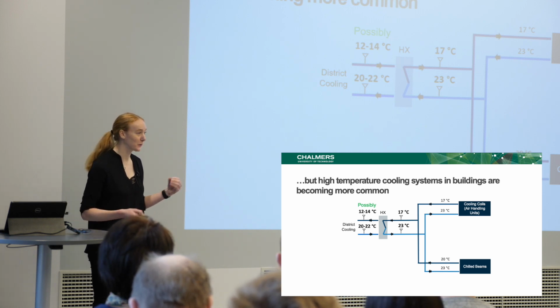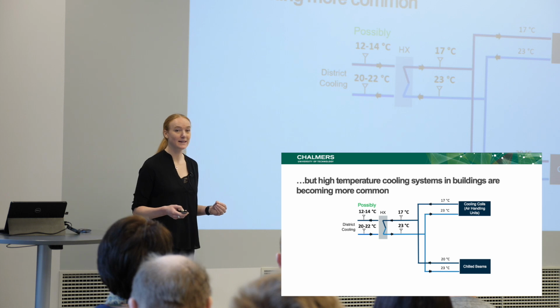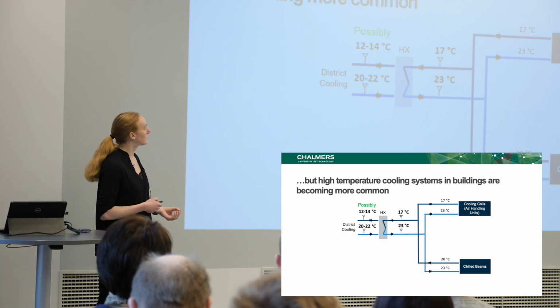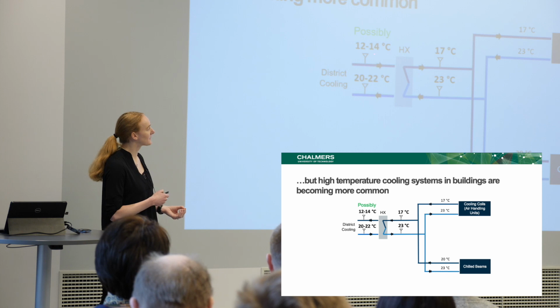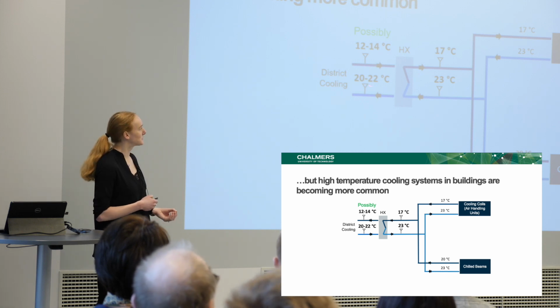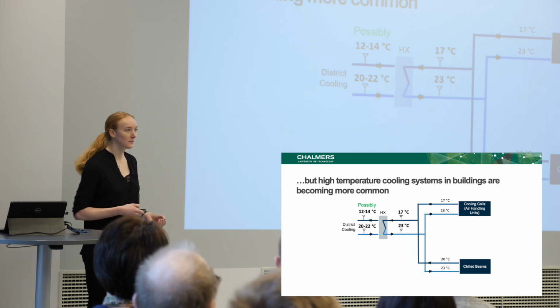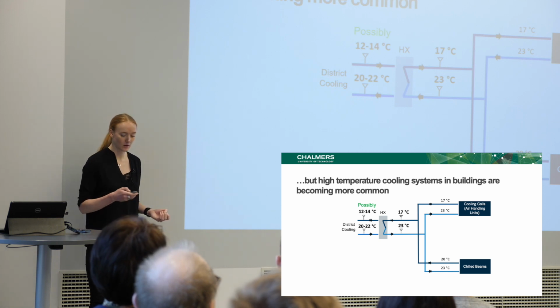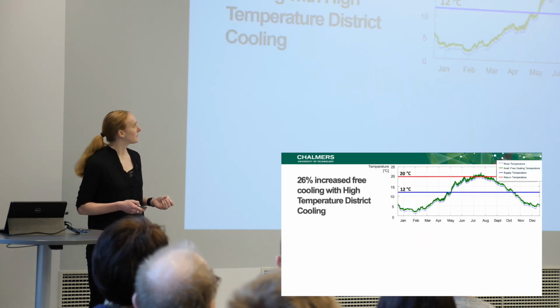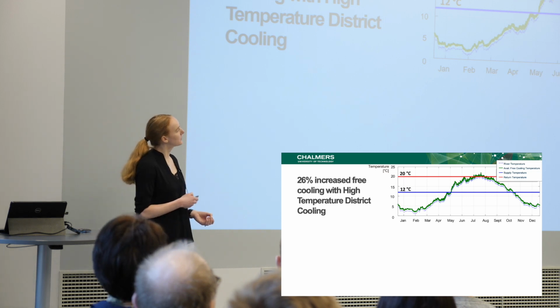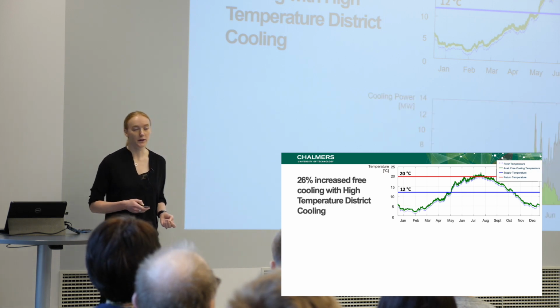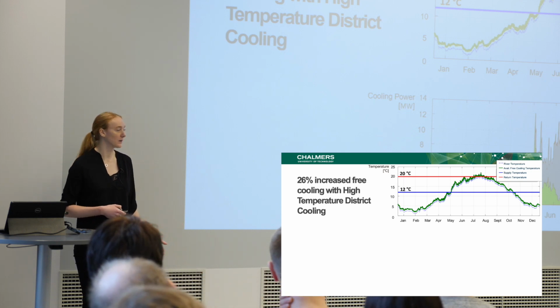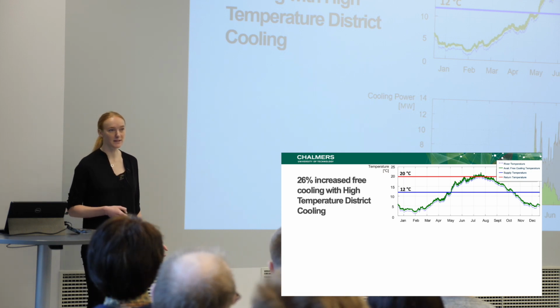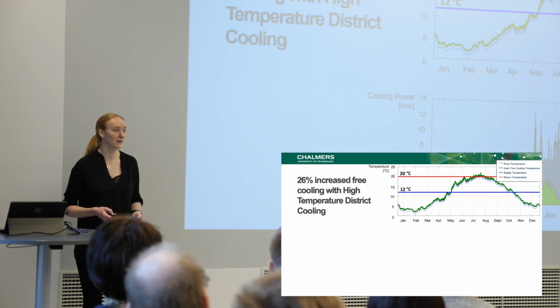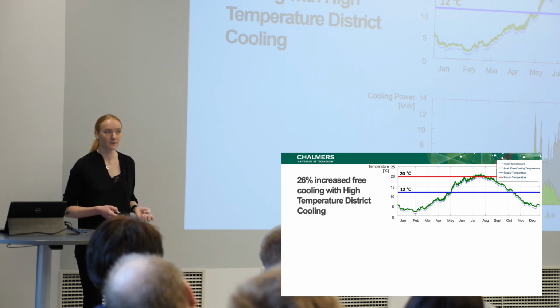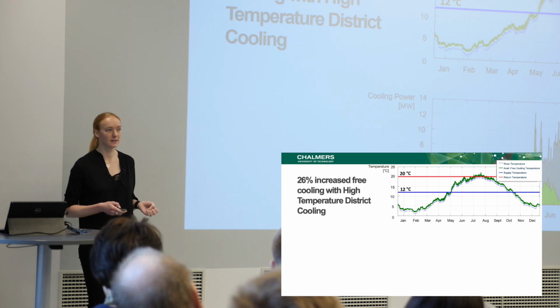If many buildings were to employ these high temperature cooling systems to supply something that is higher, around 12 to 14, and be able to get a higher return temperature, let's say 20 to 22. So with these temperatures, if we select 12 supply and 20 return for the district cooling system, for Gothenburg that would mean that the share of free cooling would be almost 55% of the whole year, more than half the cooling production of the whole year. A 26% increase.